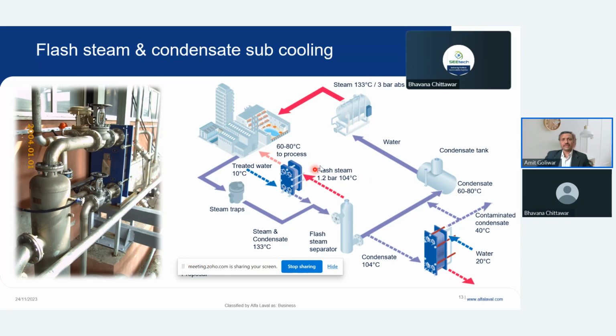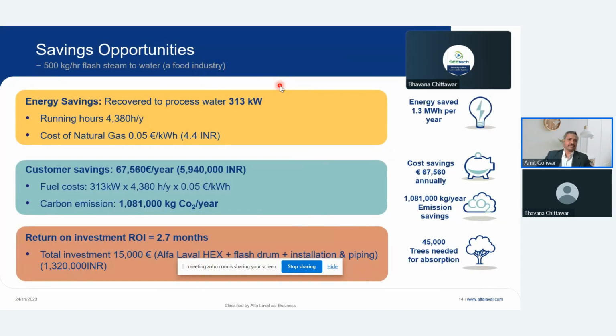And finally, what is important is saving the heat. Once you save this heat, probably you will have to generate less steam out of the boiler, and the fuel consumption probably remains the same or a little less because you are utilizing the heat. An important factor is it will be easy to manage the system because you are depressurizing the complete return line. This is a typical food industry plant where flash steam was vented, and we recovered the flash steam. And we observed that after recovering the flash steam, the payback period was just 2.7 months. And it's not only a saving of close to 60 lakh rupees, but we could also save a carbon emission of 1,081 tons per year.